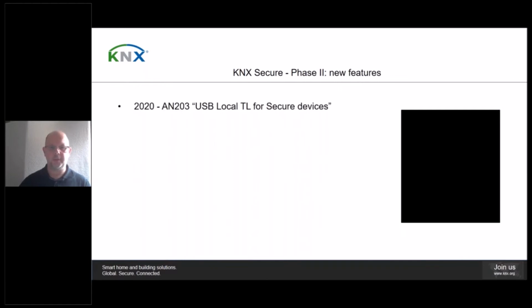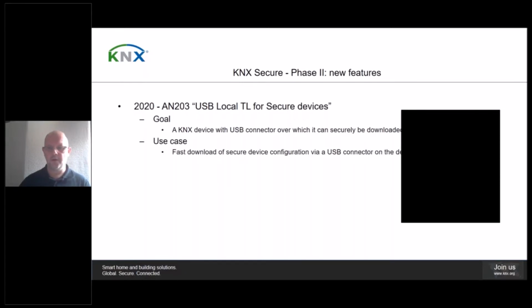Recently, we have approved the application of AN203, USB local transport layer for secure devices. The goal? A KNX device with USB connector over which it can be downloaded securely. The KNX data security specification so far focused on fixing the security for the bus communication. Local download via USB with secure telegrams was not possible. Use case? Fast download of secure device configuration.